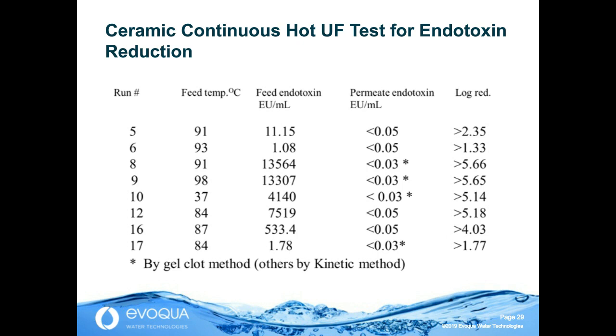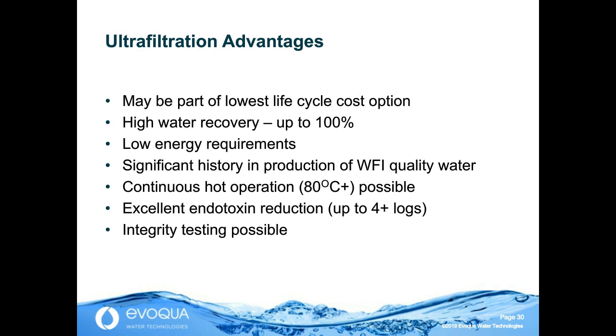UF can be part of a great low-cost solution: high water recovery up to 100%, low driving pressure, so low energy, and a significant history. Some UF elements, many, are capable of hot water sanitization. Fewer are capable of continuous hot, but some are. There is a good history of 4+ log reduction and, unlike RO, integrity testing is possible.